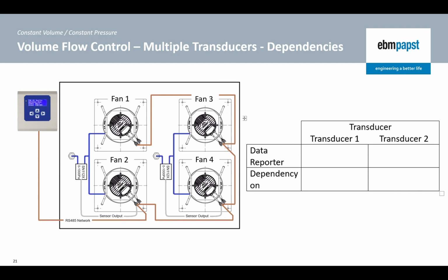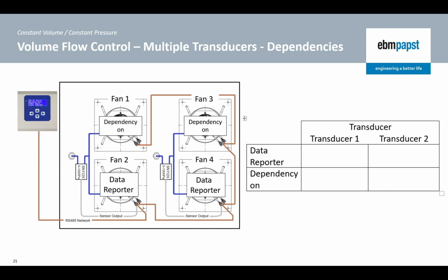This connection method has created a dependency where one fan is providing the output data which is read by the MDC and the other one is responding only to the speed commands received from the MDC over the RS485 network.